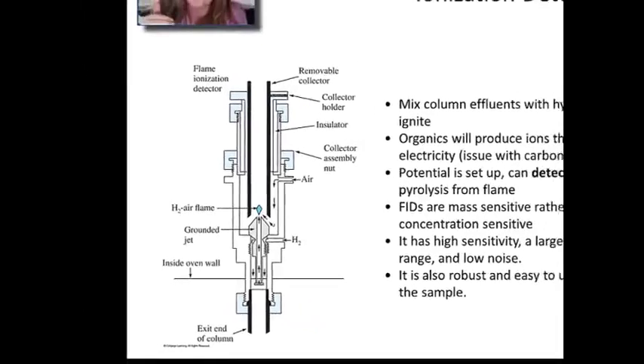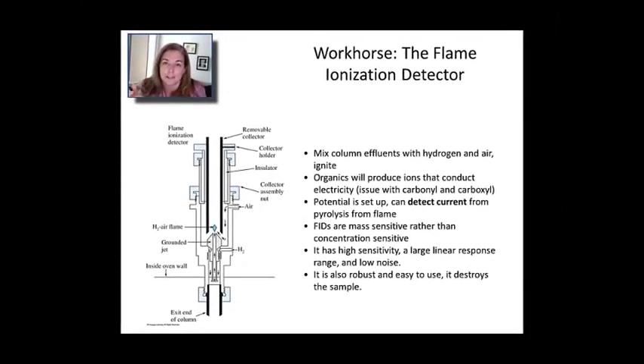As these molecules are coming off the column and they enter this little mini bomb, they're going to, in some cases, create ions. Those ions are going to actually impinge on an electrical circuit that will actually generate a current as a function of the number of ions that hit it. That ionization process is really how you initiate the detection process. That's going to be really insensitive to the chemical nature of the materials coming off of the column. And it's also going to be really sensitive. FIDs are great systems with good enough detection limits to work with capillary columns over a wide, wide range of organic systems. They're robust and easy to use. Of course, they do destroy the sample.